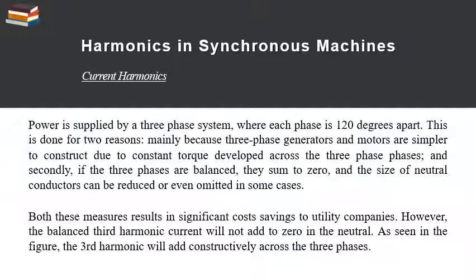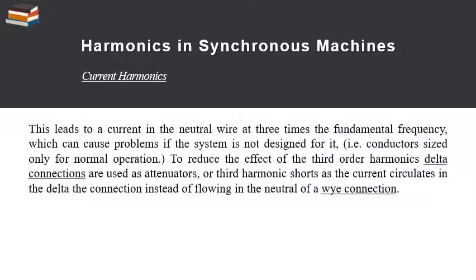However, the balanced third harmonic current will not add to 0 in the neutral. As seen in the figure, the third harmonics will add constructively across the 3 phases. This leads to a current in the neutral wire at 3 times the fundamental frequency, which can cause problems if the system is not designed for it, that is, if the conductor is sized only for normal operation.